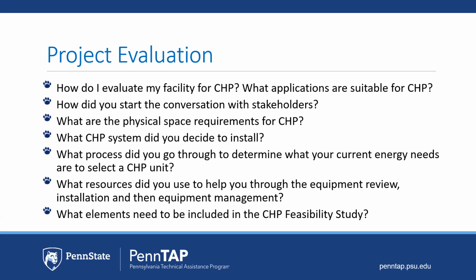It's important that there be enough energy requirements in electric and in heat, and that the CHP waste heat be paired with the site-specific thermal requirements, which is the $64 question with CHP. If you're placed into a heat load following mode, you're often just wearing out your machine as you're trading dollars with the utility. So if you have a heat load you can operate consistently for enough hours, that'd be the first check for CHP.